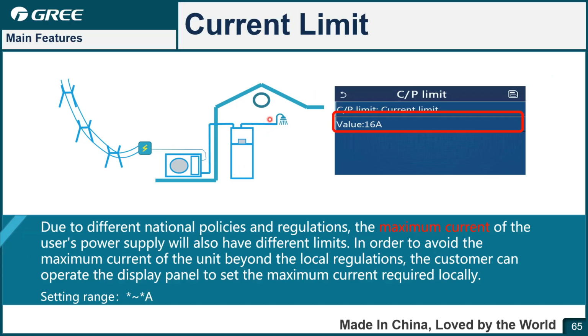Next one is the current limit. Because of country regulation and policy, maybe the government does not allow too high a current for the grid. So for the VERSATI 3, there is a function for the power limit. This is the default one, 16 ampere. However, you can change it to between 0 and 50 ampere. You can set it by yourself. And if the running current is too high and exceeds the limit, the unit will stop. So there is no worry about the current being too high.